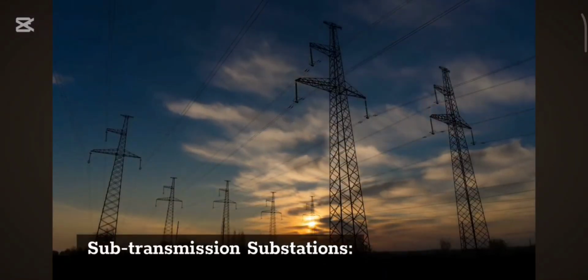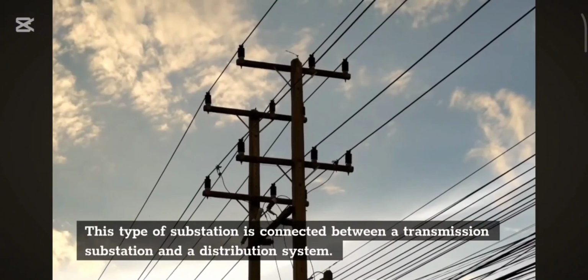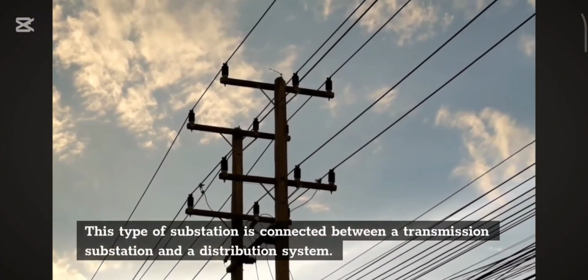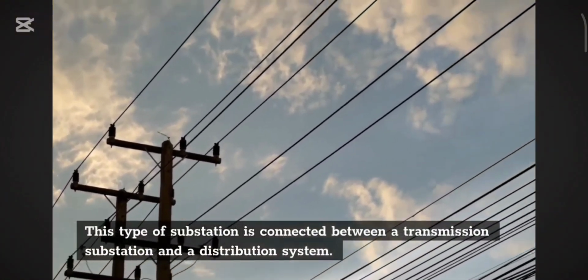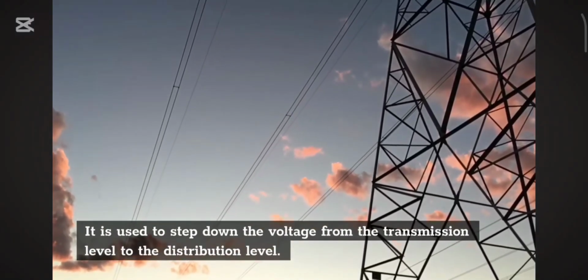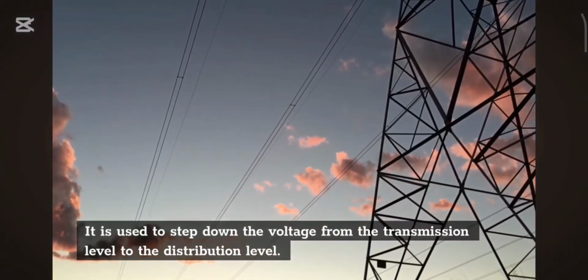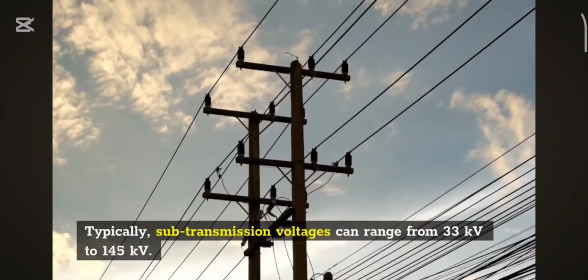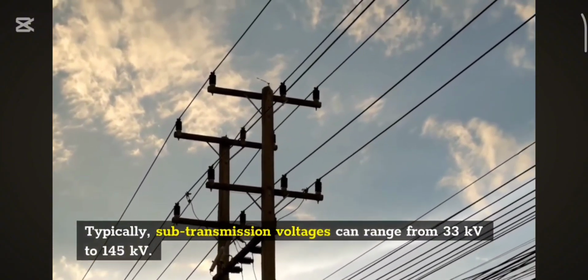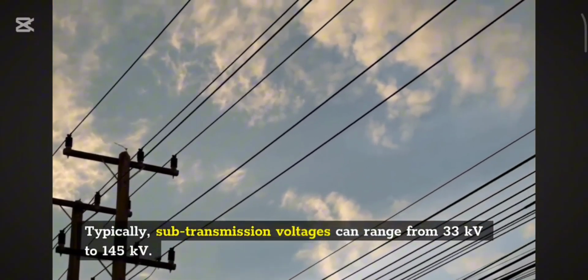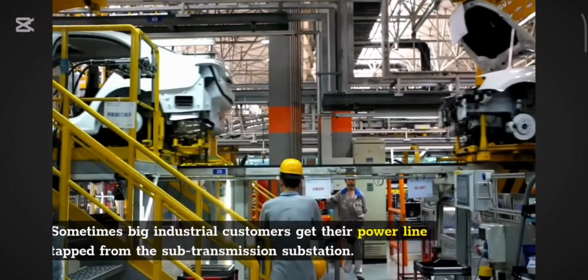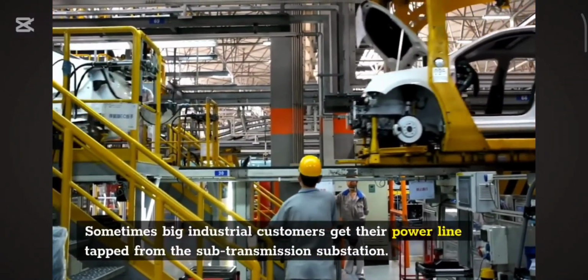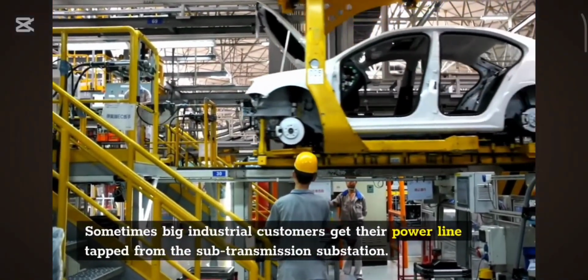Sub-transmission substations. This type of substation is connected between a transmission substation and a distribution system. It is used to step down the voltage from the transmission level to the distribution level. Sub-transmission voltages can range from 33 kV to 145 kV. Sometimes big industrial customers get their power line tapped from the sub-transmission substation.